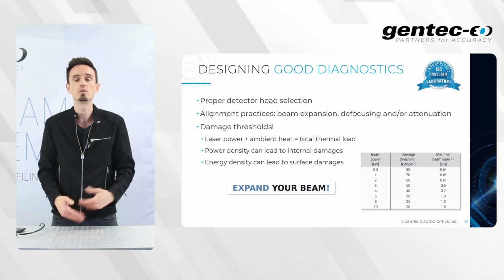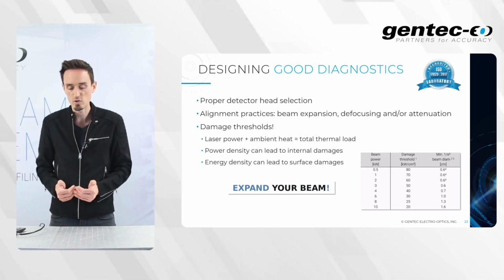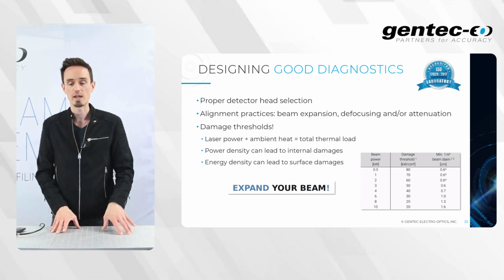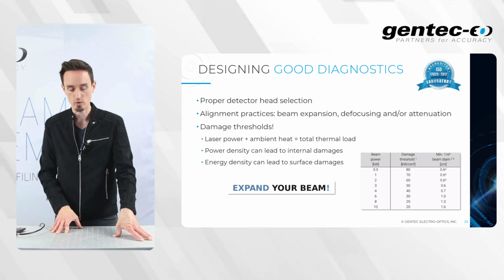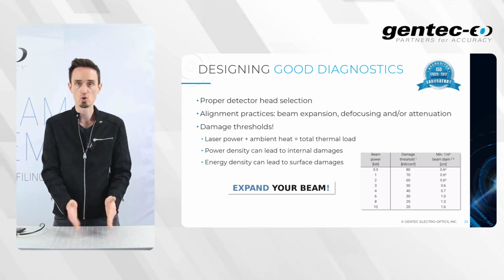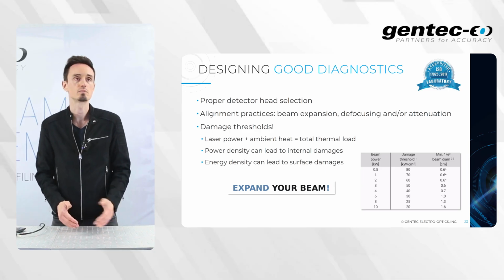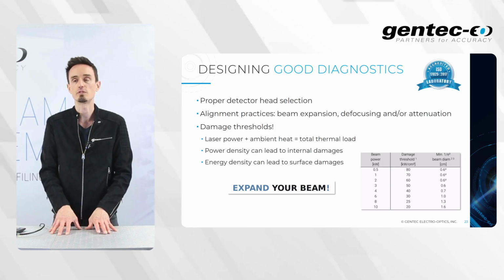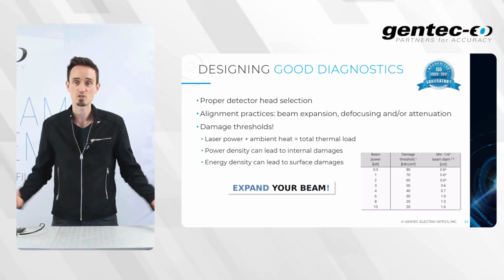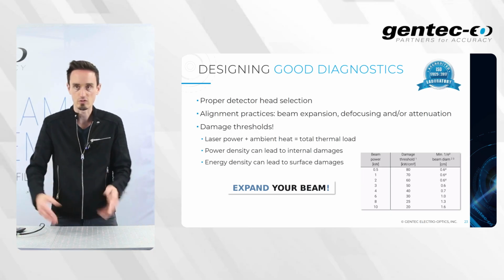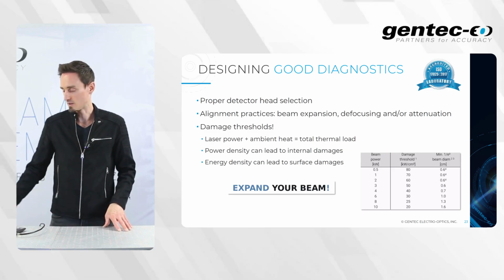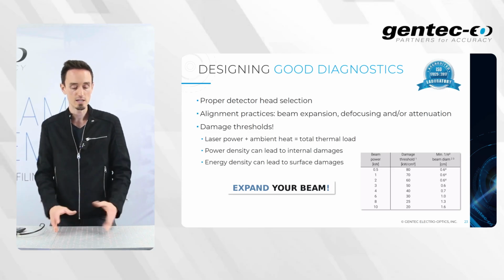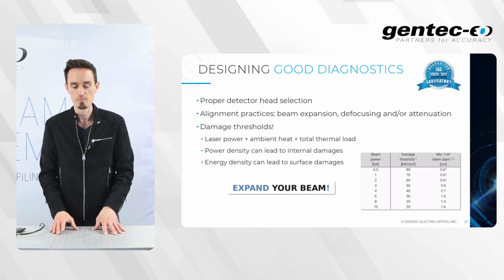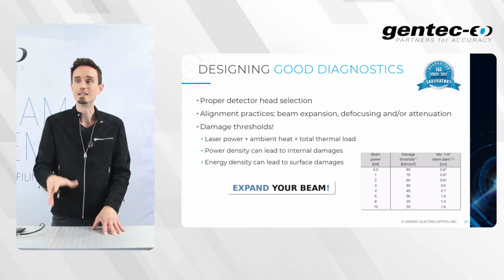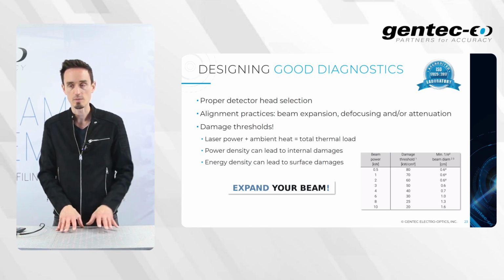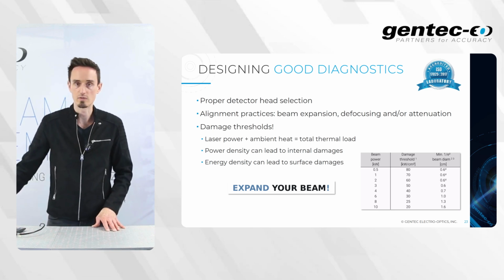touching the detector, that could usually lead to internal damages from overheating. Then energy density damage threshold, which is the energy in joules divided by the surface area, potentially leading to surface damages. And you could have a combination of the three things, resulting in some bad scenarios and bad damages on the detectors. The key here most of the time is to expand the laser beam. Damage thresholds are well listed in given conditions, but depending on the application, they could vary quite a lot.